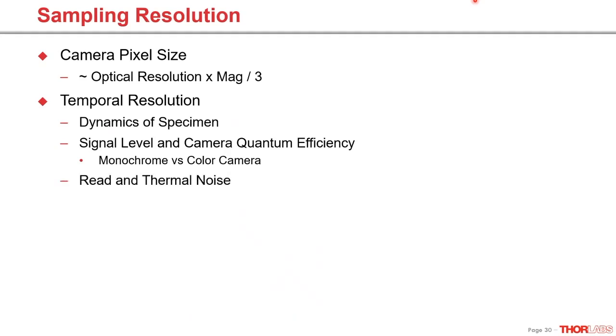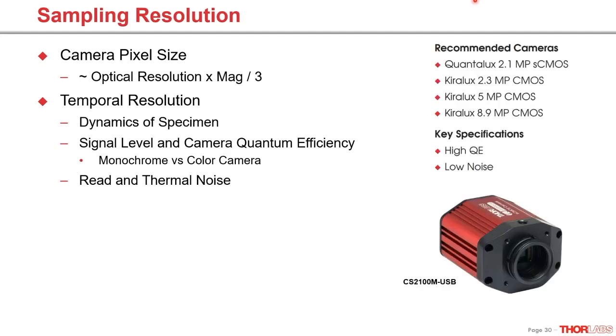Regarding camera noise: the faster your readout speed, the higher the read noise. Longer integration times may require camera cooling as thermal noise comes into play. We have a few recommended cameras in our brochure — they're all monochrome cameras with high quantum efficiency (high sensitivity) and very low noise. Please look at Martin's webinar, which went into extensive detail on picking a camera.